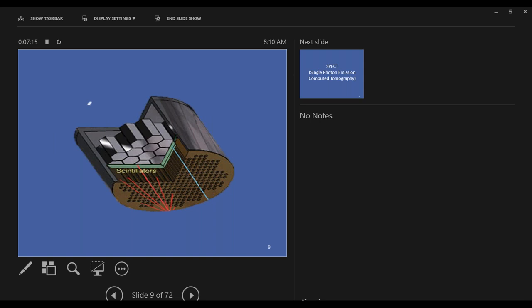The next portion of the camera is called a scintillator, which is basically a sodium iodide crystal. The gamma radiation passes through the collimator holes, hits that crystal area, and causes it to emit light beams as it reacts. Those light beams correspond to where the radiation is in the body — it's kind of like a reverse x-ray. Instead of radiation penetrating the body to make an image, the radiation is coming out of the body to make an image. Behind the crystal are hexagonal photomultiplier tubes that work almost like a photo diagram, making an image when lit up. The computer then assembles the image based on the position and signal intensity of each photomultiplier tube.